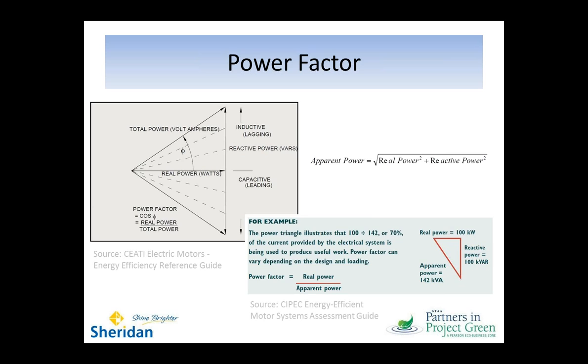So our induction motor is going to end up consuming the real power to actually spin the rotor. It's going to consume the reactive power to create the magnetic field. And in the diagram on the left here, what you see is this definition of real power as watts or kilowatts. The reactive power is measured in VARs, volt amperes reactive, or kVARs, depending on whether it's thousands of volt amperes or just VARs. And this is a right angle relationship. So you can see on the top right that apparent power is described as the square of the real power and the square of the reactive power. Take the square root of that to get the apparent power, or the hypotenuse of the two. So there's a relationship there.